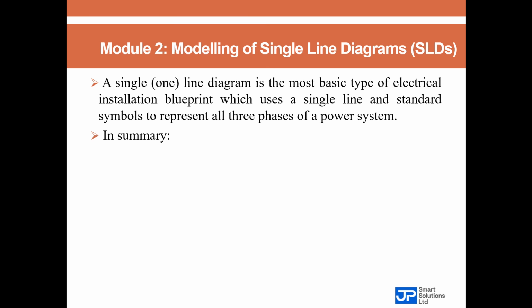However, in the determination of the stability of a system under transient conditions resulting from a fault, it depends on the speed with which the relays and circuit breakers operate to isolate that faulted part of the system. So this information about circuit breakers and relay configurations will be of extreme importance for such a study. Therefore, they are required on the single line diagram.